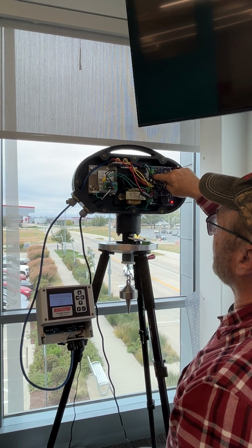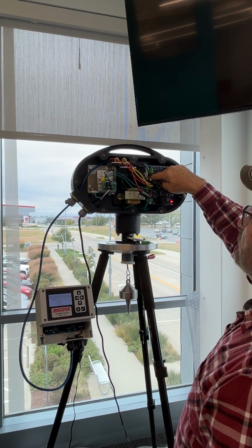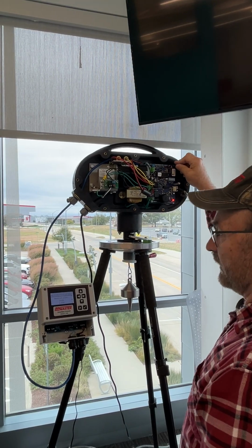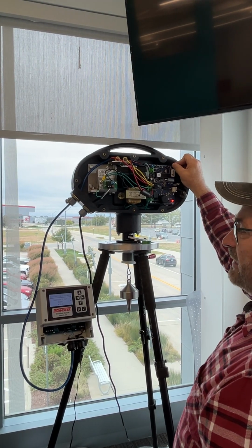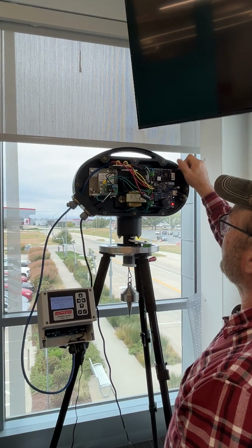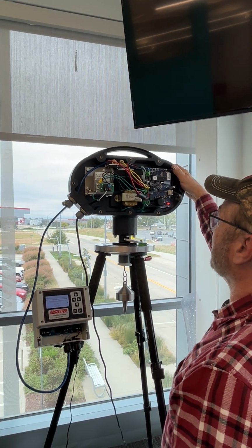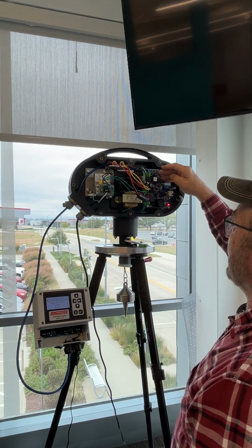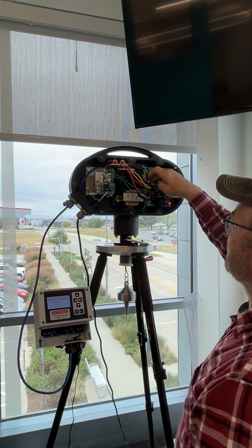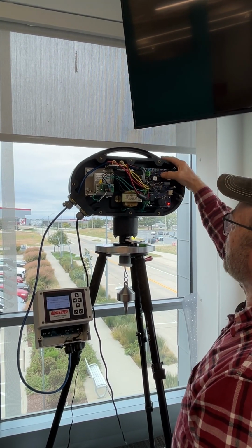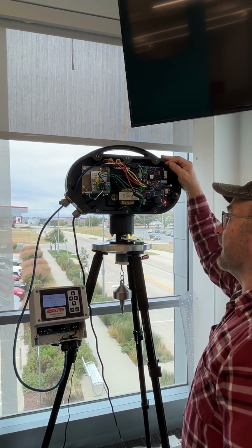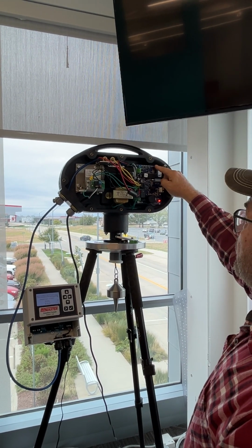It could be the communications chip. It could be the over voltage devices. Since these are up high in the air, they do get exposed to lightning and that can do damage. If it's a bad enough hit, it can get through all the way and even damage the processor, but that's rare that happens. But these lights can tell you a lot.